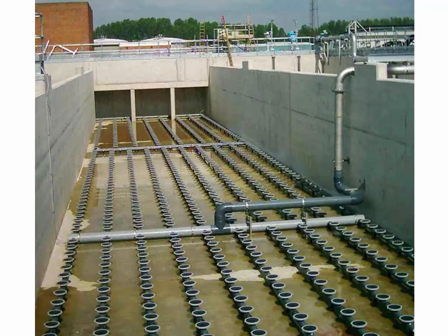If the bubble is big, it can float to the surface very quickly. It's kind of similar to when we were talking about particles and how when they're settling downward, a big particle can settle fast through water and a small particle settles slowly. Because the larger it is, the settling velocity is larger because the ratio of drag to weight is different. Whereas a very small particle like this is going to have a lot of drag as it moves downward through the water. So these bubbles are going up. Big bubbles would move quickly, and that's not what we want.